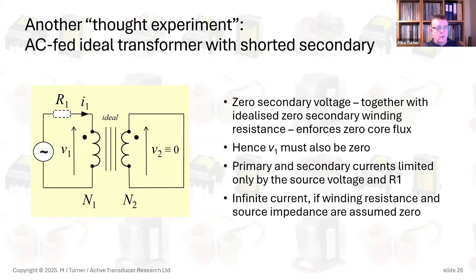But if the magnetic coupling is imperfect, what happens then? Well, some of the magnetic field is going to make its way through the more difficult path of not going around the core, and most of it will go around the core, but a little bit of it will leak around the local windings. And with that enormous current flowing in the primary winding, with no flux in the main core, we will establish a leakage field around the primary winding that doesn't link the secondary. So again, we've got a big current now in this short-circuited transformer, no flux in the core, but a little bit of flux locally around the primary. And the flux divided by the current is called the leakage.